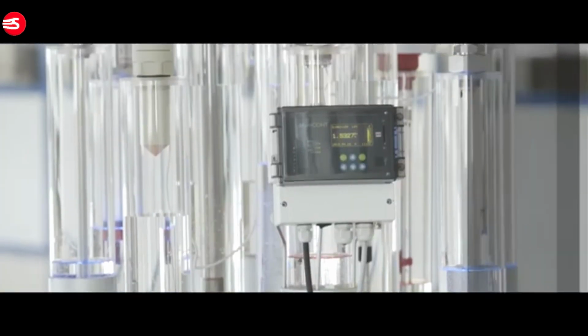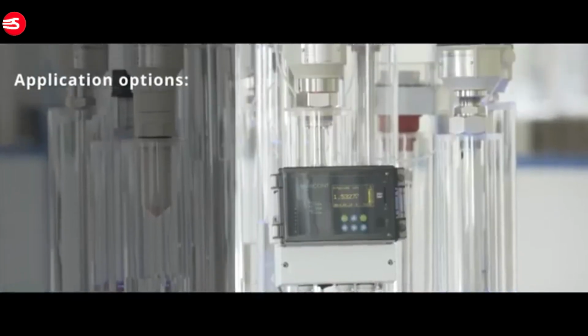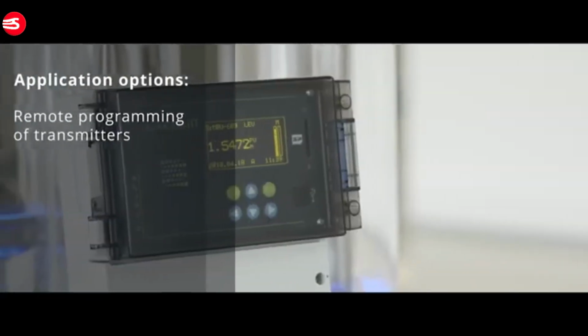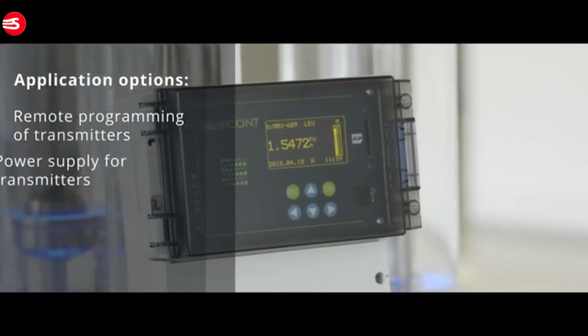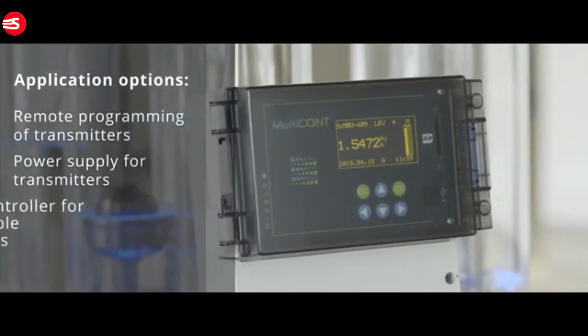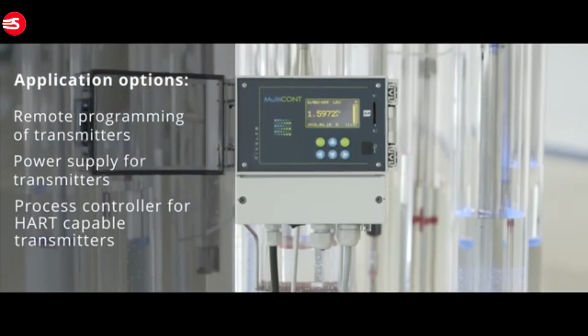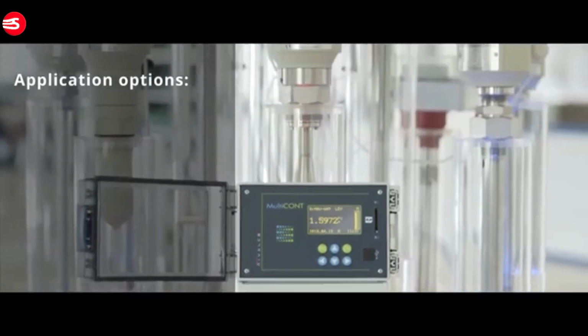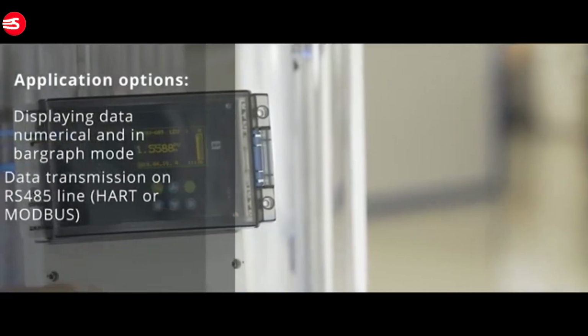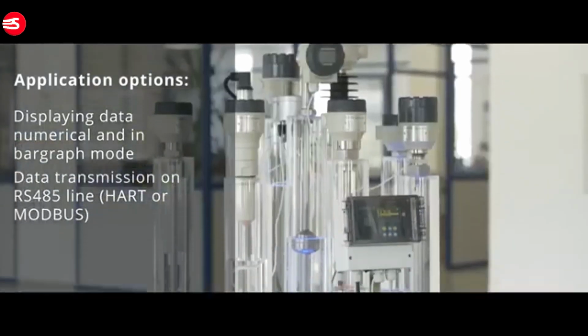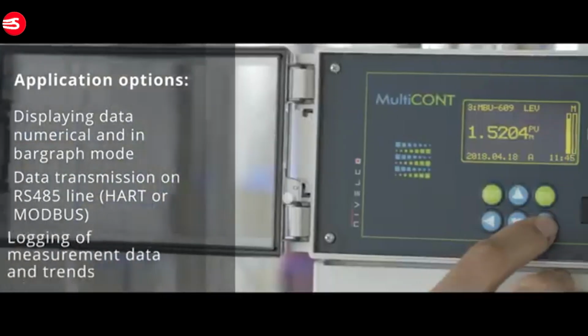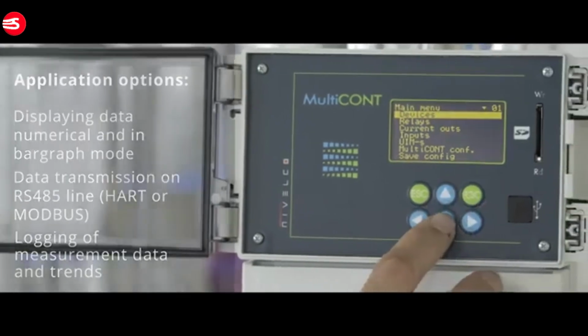Multicont process controllers are recommended for the following tasks: easy remote programming and displaying of transmitters, power supply for two-wire transmitters, flexible process controller for HART-capable transmitters, displaying measurement data numerically and in bar graph mode, data transmission on RS485 line with HART or Modbus protocol, trend logging or logging of flow measurement data.